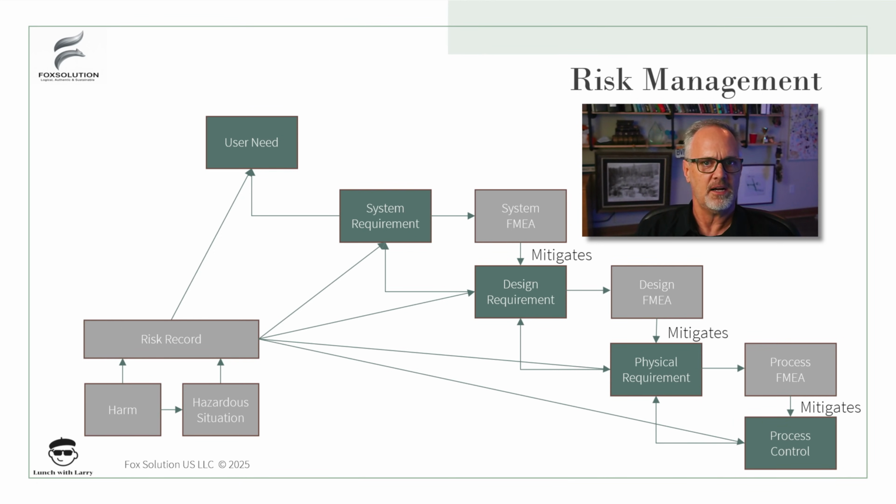There's all kinds of things that need to happen to assure that the hazardous situation where that exposure happens doesn't occur. So things from aseptic transfer techniques, storage, the sterilization process itself, all the design requirements around the design of the sterile barrier bag, for example. So all kinds of things that we need to take into account when we say that we've controlled that hazardous situation. It really needs to be a systems level view.